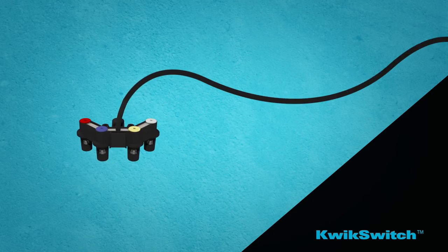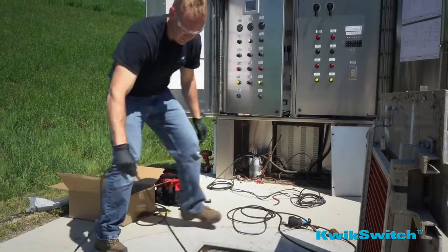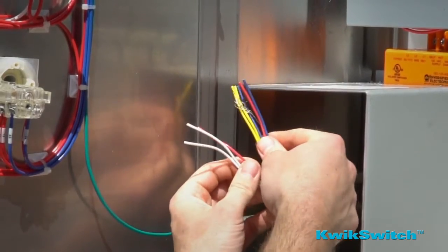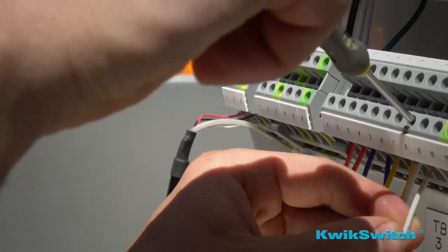The KwikSwitch utilizes a single multi-conductor direct burial-rated cable from the unit to the control panel, eliminating the need to pull multiple float cables through conduit in replacement situations. The single multi-conductor cable includes four pairs of color-coded wires and a ground shield for easy and clean field wiring.